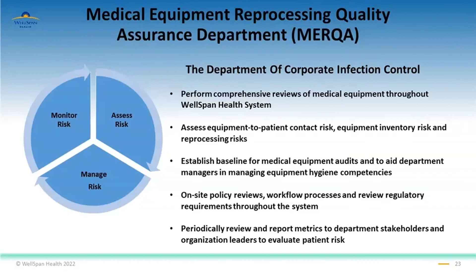Documentation of the on-site observation requires auditors to have excellent writing skills to accurately document the current state cleaning process, including any deviations from the equipment manufacturer's instructions for use. And then we make recommendations for reprocessing compliance. And if the equipment reprocessing is observed to be severely outside of the manufacturer's instructions for use, auditors will elevate the observation in real time to me, the MERQA director, for further guidance or elevation to senior leadership.